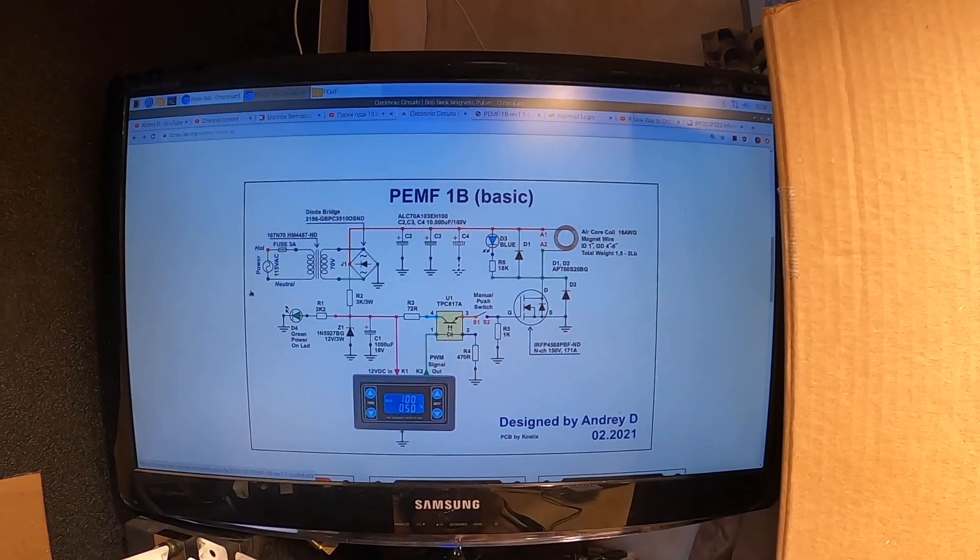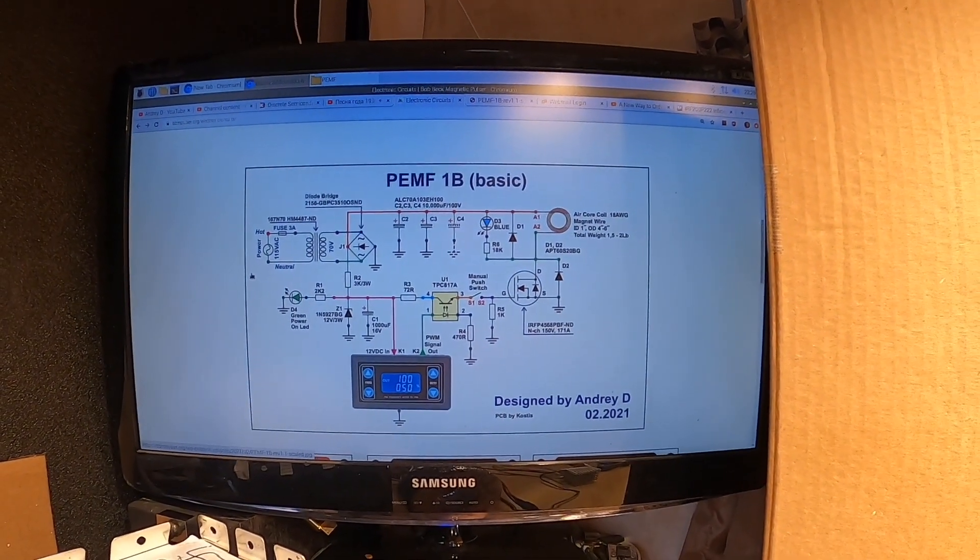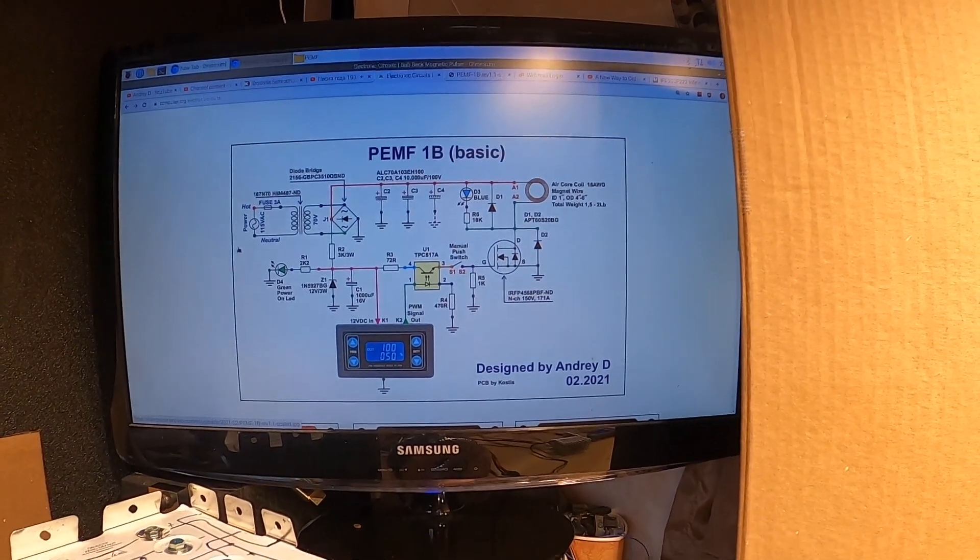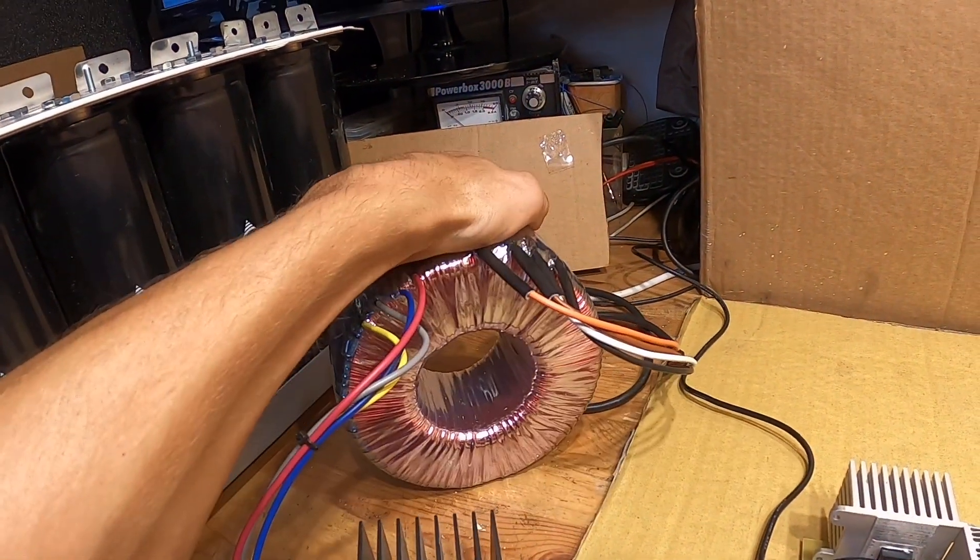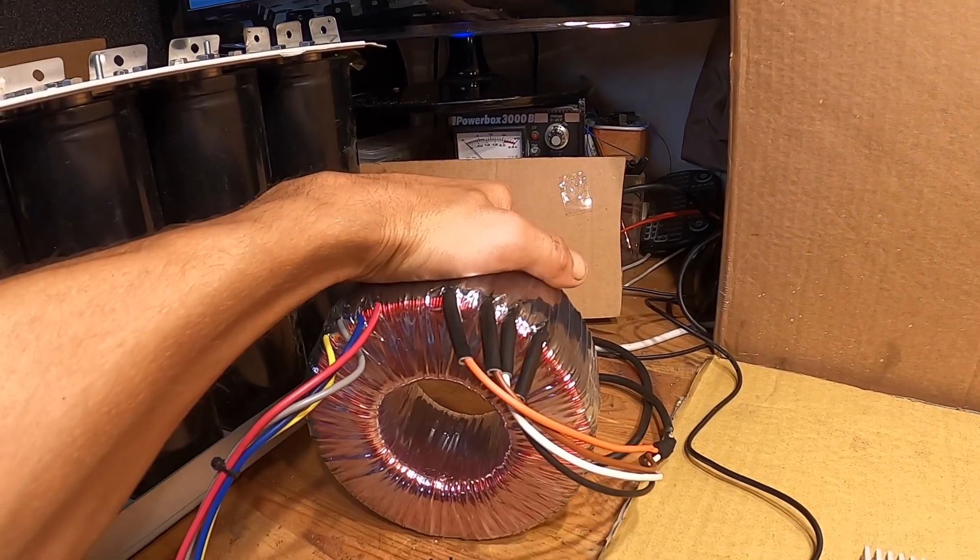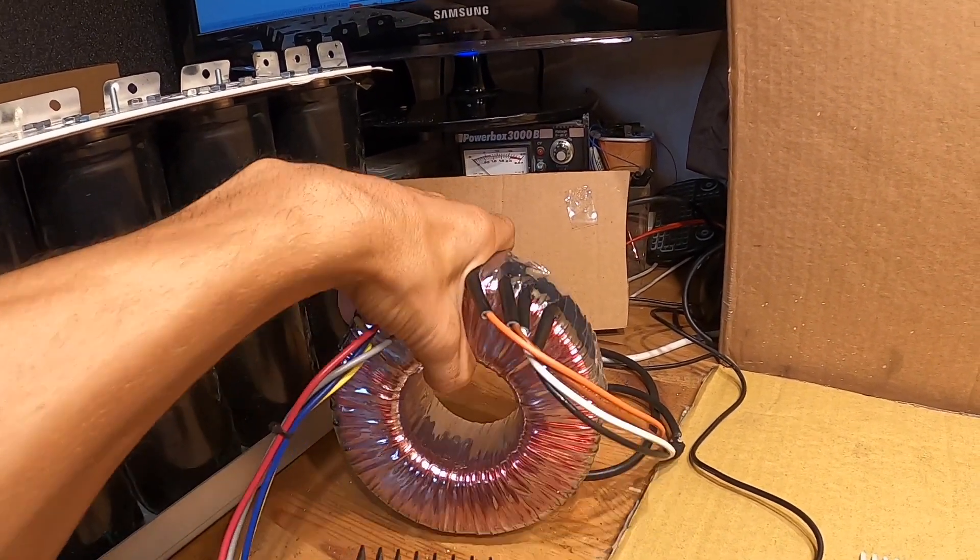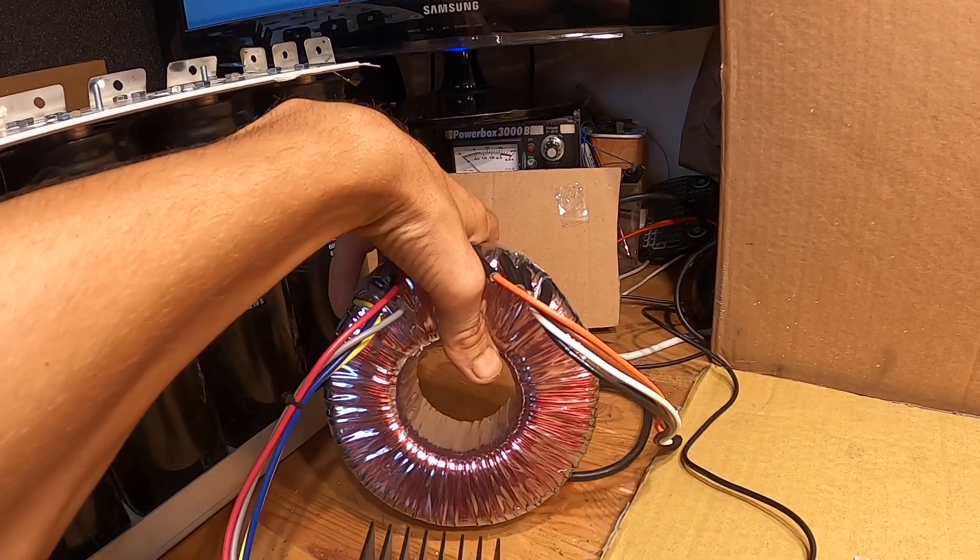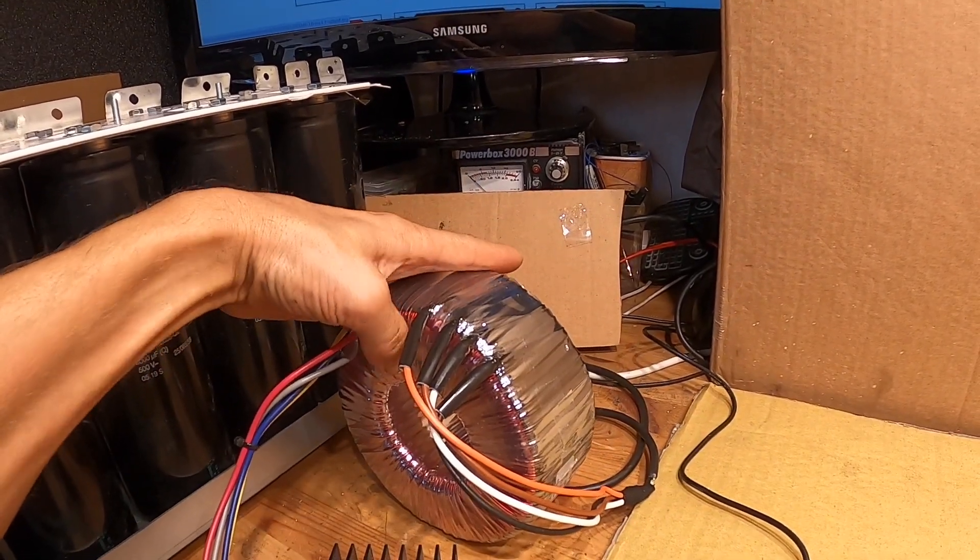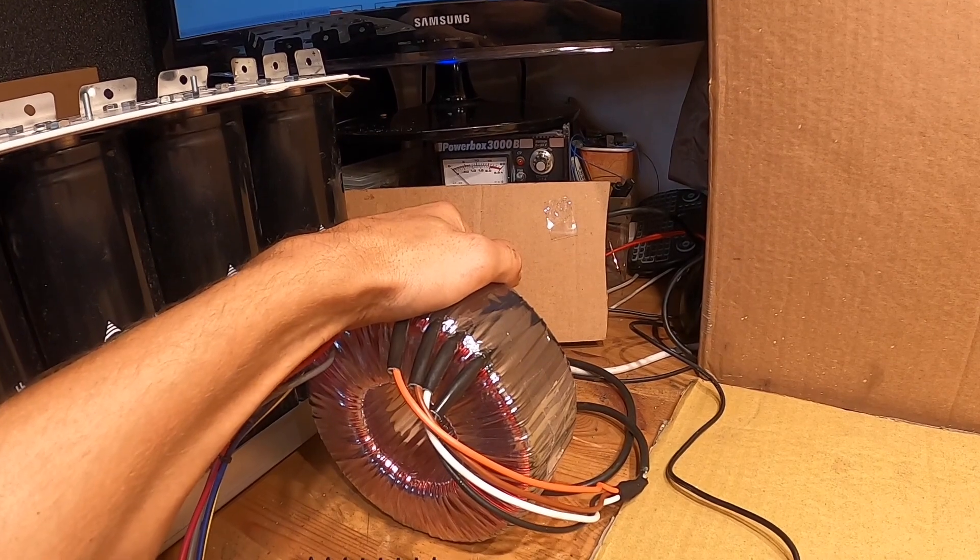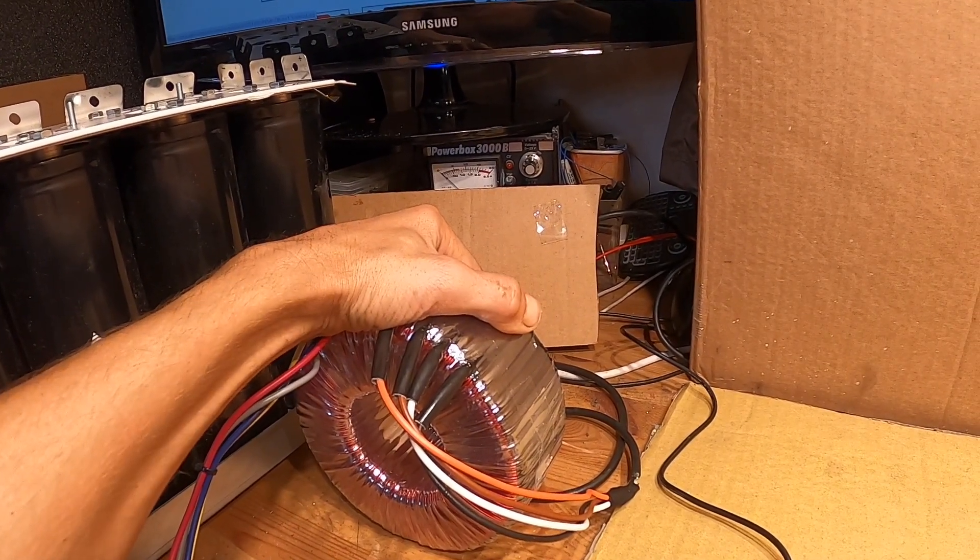Okay, so I'd like to go over components that I'm using for this circuit here. Well, I don't have a 70 volt transformer but I have 120 volt transformer, and so I will go ahead and use 120 volt for this test.